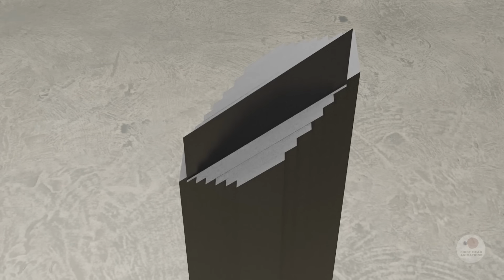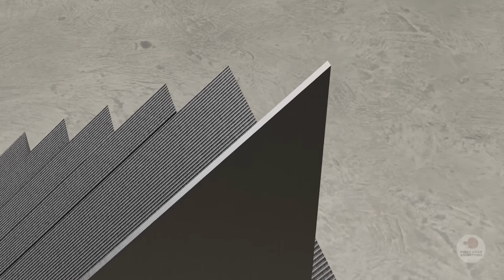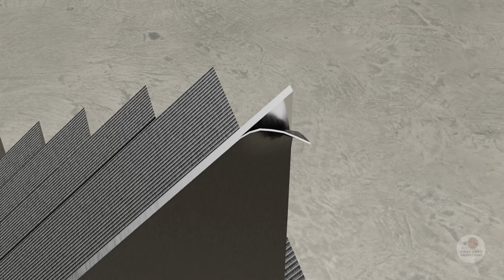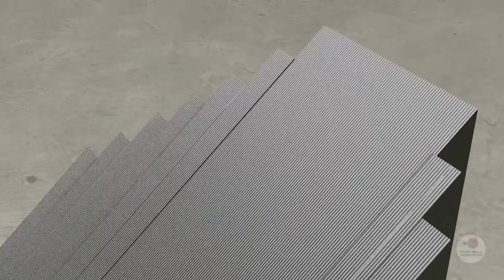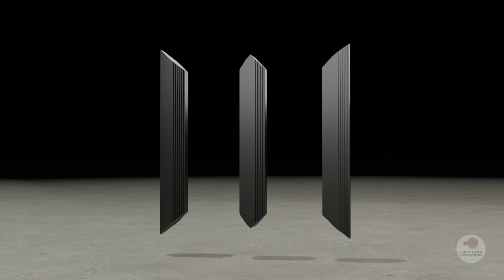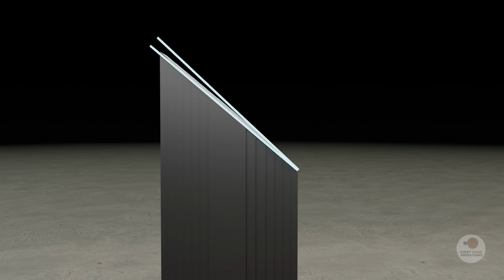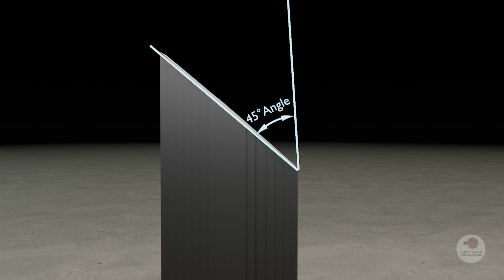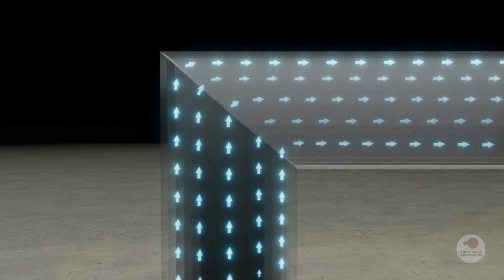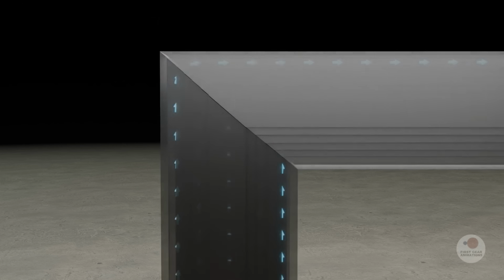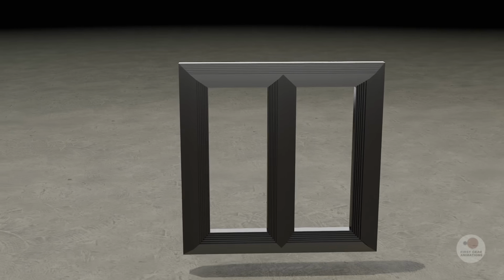To prevent this, each lamination is coated with a thin layer of silicate-based ceramic, known as C5 insulation. This coating is extremely thin to allow maximum steel in the core, yet strong enough to withstand high operating temperatures and break the path of eddy currents. To ensure a smooth magnetic flux, the corners of the core are mitered at 45-degree angles. This allows the magnetic flux to easily turn the corner, minimizing vibration and heat.